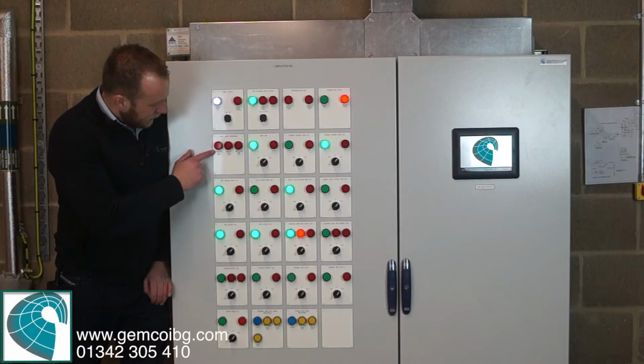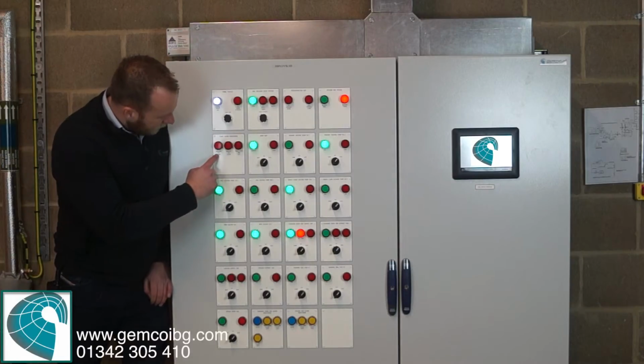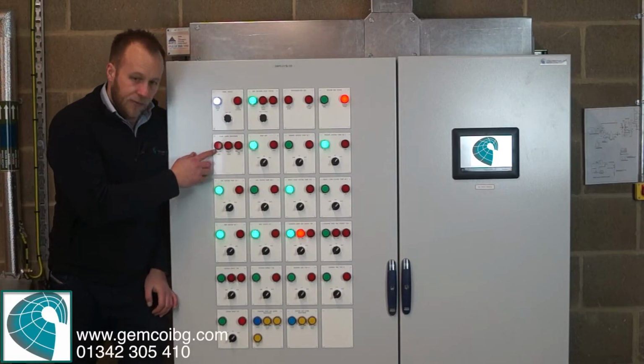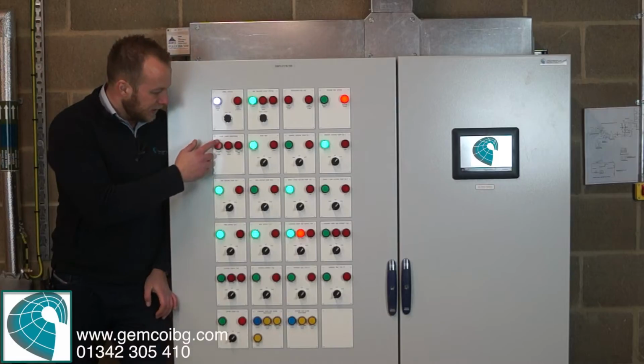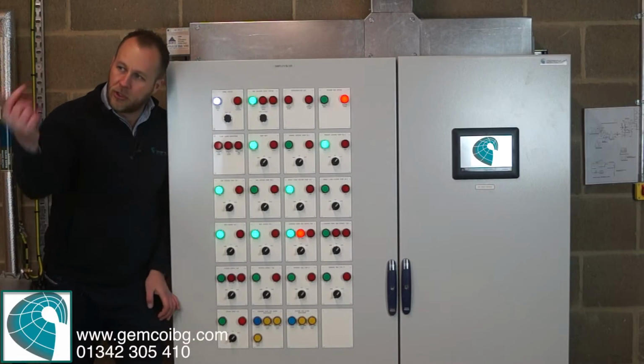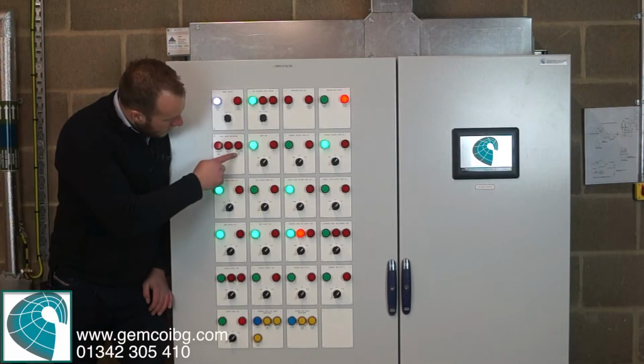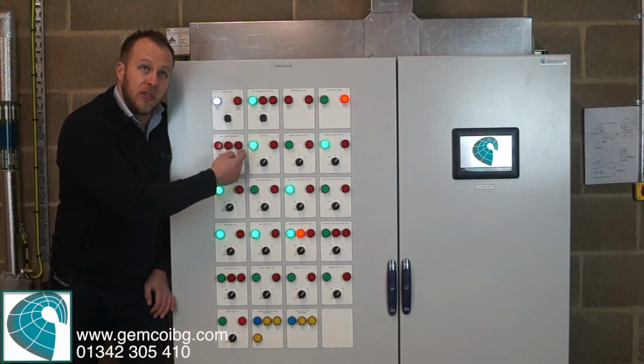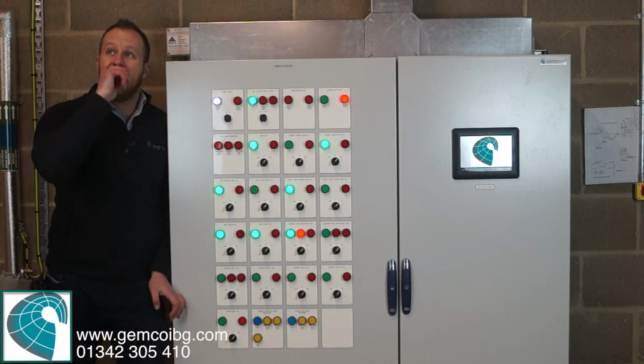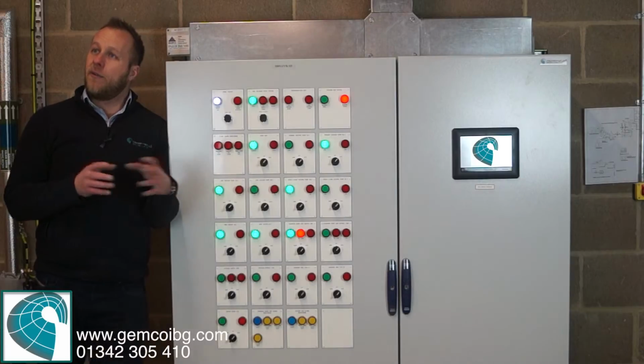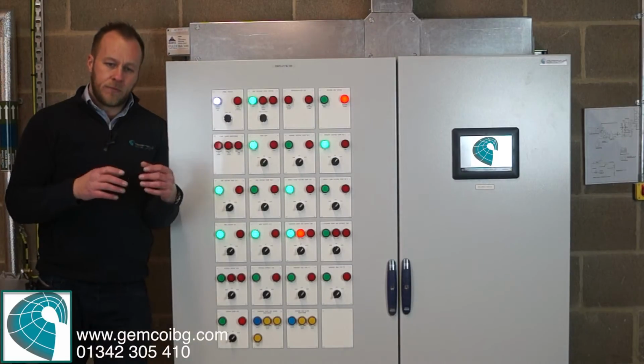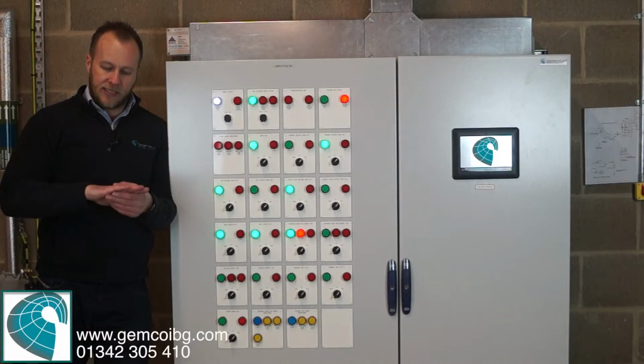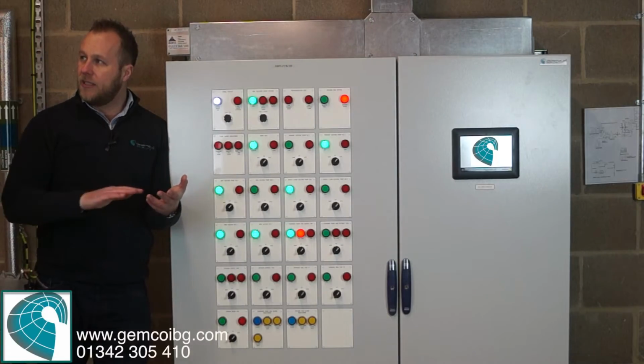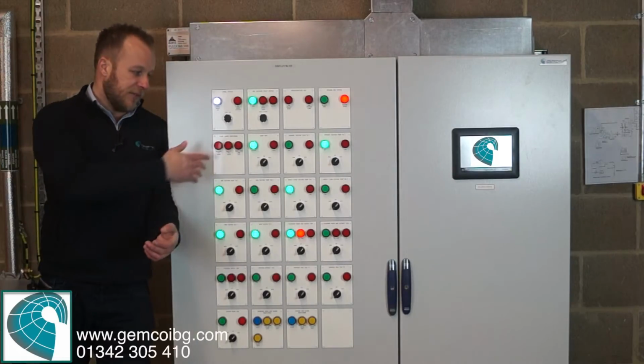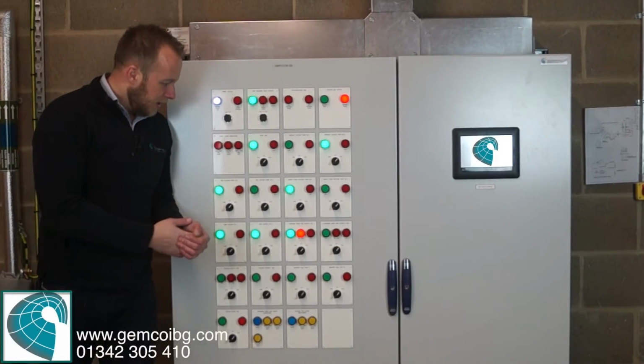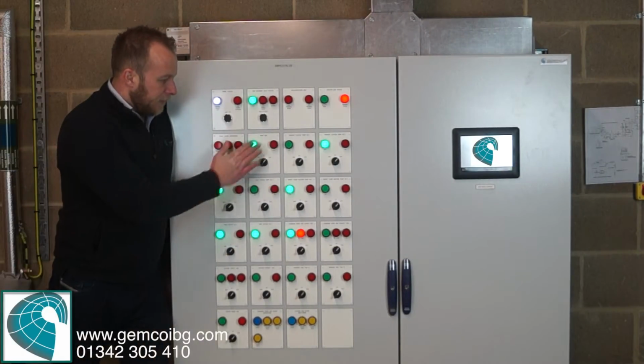Other plant monitoring alarms, these aren't important, but there's a hydromag unit, which is a water conditioner. Just letting you know if that unit's got an alarm, if it needs some service or maintenance. And the booster set alarm, that boosts your cold water into the system via this tank. And then the underfloor circuit high limit. So we've got a high limit stat up on the circuit that serves the underfloor heating. The reason we put that on there is because underfloor heating circuits need to be protected, so they should only be 60 degrees on the primary side. So if it goes anywhere above 70, we just raise an alarm just to let you know that you've got a hot temperature.